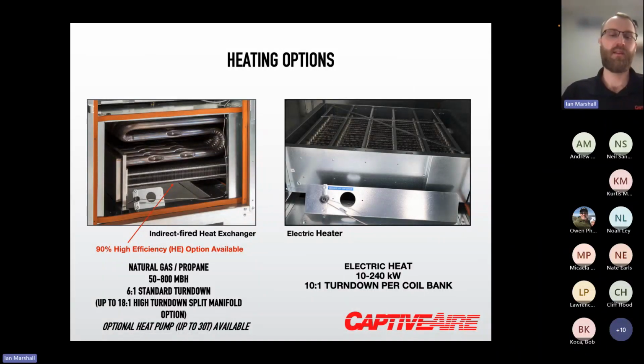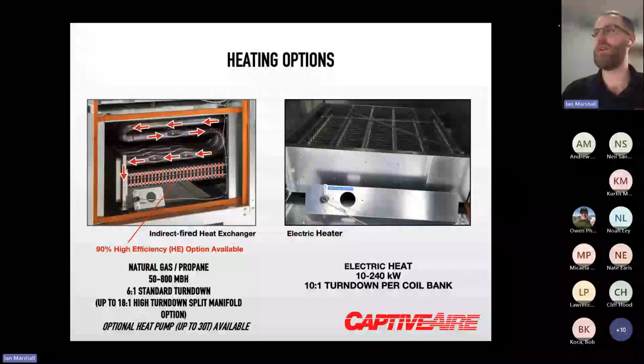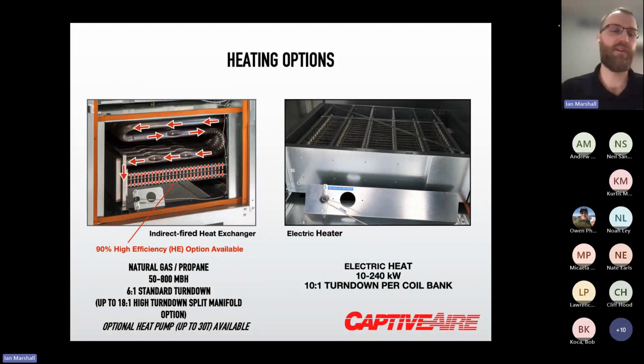For heating options, we have a few different choices. We can do indirect fired heat or electric heat. We also have heat pump available, as well as a hot water coil option. For the indirect fired heat option, our standard is an 81% efficient heater. The one pictured here is actually a 90% efficient indirect fired heater. We don't utilize these too often because they are fully condensing, but it's shown here for reference. For the indirect fired, we go from 50 MBH up to 800 MBH with a 6-to-1 turndown standard, or we have an optional split manifold high turndown up to 18-to-1. Again, it's fully modulating, not 6 stages or anything like that. It's fully modulating between 100% output and one-sixth of that.